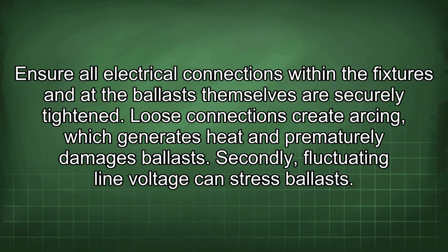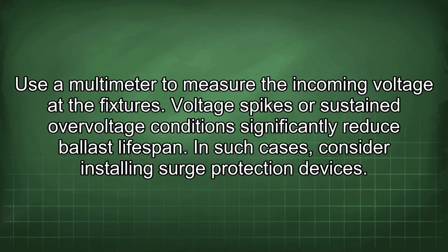Secondly, fluctuating line voltage can stress ballasts. Use a multimeter to measure the incoming voltage at the fixtures. Voltage spikes or sustained over-voltage conditions significantly reduce ballast lifespan. In such cases, consider installing surge protection devices.